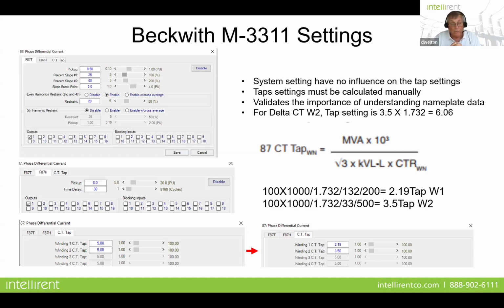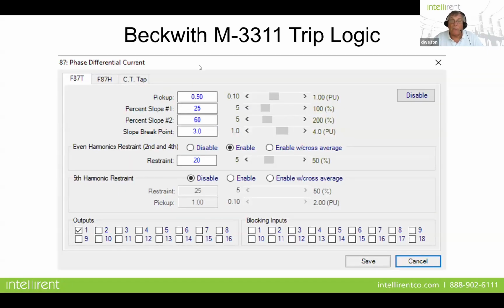Now, we can make quite a few errors here. If we say we invert the CT ratios on the primary and secondary side, you're going to have a problem. If we don't put in the right voltage levels, if we don't put in the right configuration in terms of how the transformer is connected. Okay, so this is very important to pay attention to. So what we see here in the differential setting, we have a minimum pickup of 0.5 per unit. And I'll explain that when we look at the slopes. Slope setting 1, slope setting 2, and a slope point break.